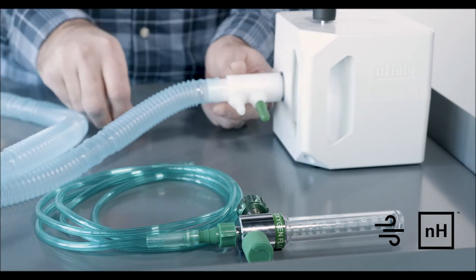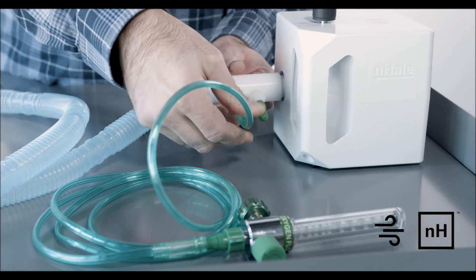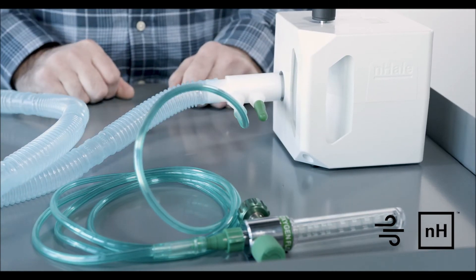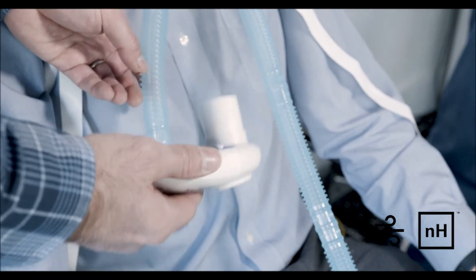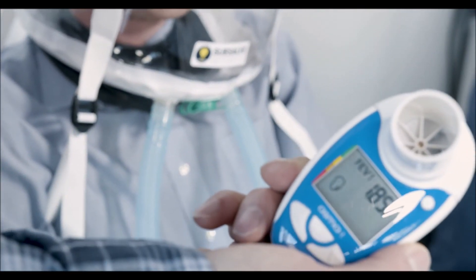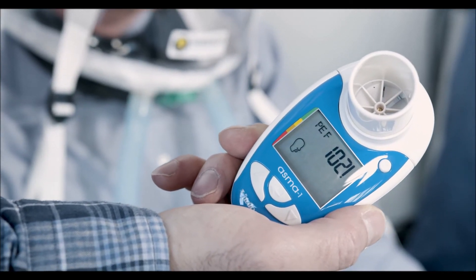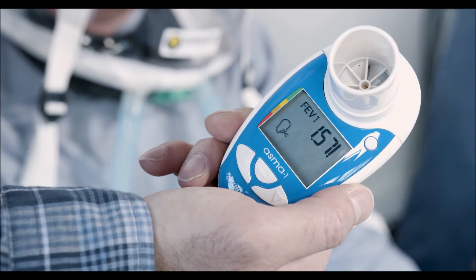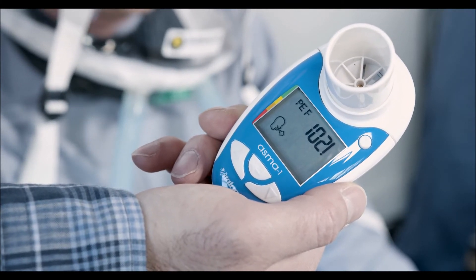To deliver therapeutic oxygen, simply establish flow from the oxygen supply. To boost to high oxygen fractions, two oxygen supplies may be used. Flow should be periodically checked using a peak flow meter — simply activate the device and place it after the viral filter for a reading. If flow is decreased over time, simply change the filter. A reference chart is provided to guide adjustments to pressure and oxygen.